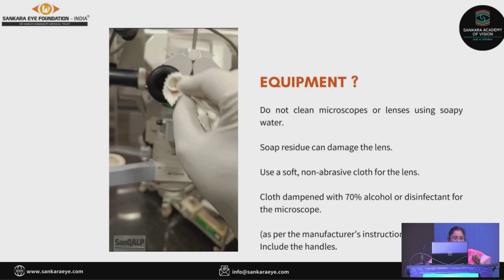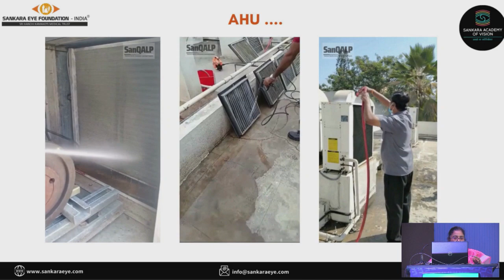This is the AHU cleaning. As I mentioned, this is the inside part of the AHU which is being cleaned for the dirt and the muck. And these are the pre-filters which are being washed and cleaned. So usually only the pre-filters and the AHU area can be cleaned. HEPA filters should never be removed by the hospital staff. Usually the inside filters are cleaned by the manufacturer.